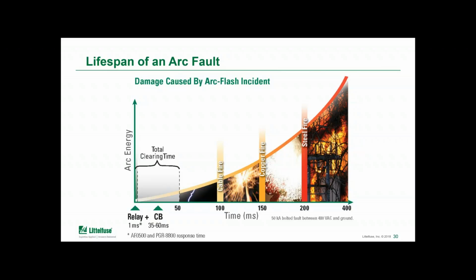Most applications would be using a circuit breaker with a shunt trip input, but even if you factor that in, a typical breaker operating time, shown there, of 35 to 60 milliseconds still puts the overall clearing time below the typical time needed for the cable to catch fire, and can significantly reduce the incident energy compared to not having that tripping device.